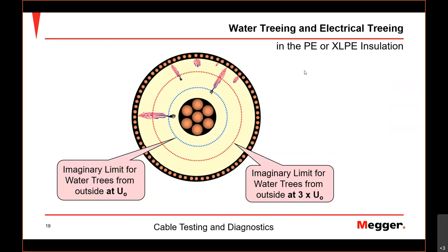There's a table that says how fast these trees grow at what voltage level, so that would be 60 minutes. Now, if you do this monitored withstand diagnostic, MWT, you do a VLF test, and at the same time, you simply connect the coupler and watch what partial discharge is doing. And you would see, oh, there's partial discharge. After maybe 1 minute, there's partial discharge setting in. Oh, so I have an electric tree. And then you could stop that measurement right away and say, oh, I have an electric tree at 325 meters. You would already have a pre-location, right? That would be right after 1 or 2 minutes.